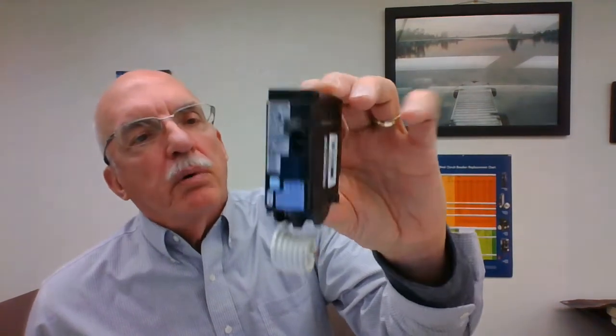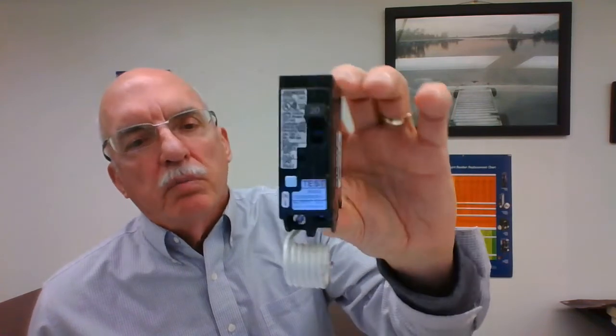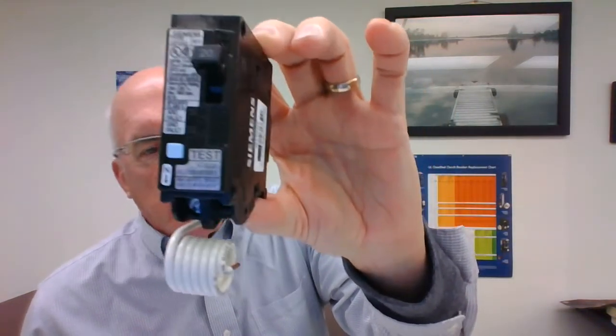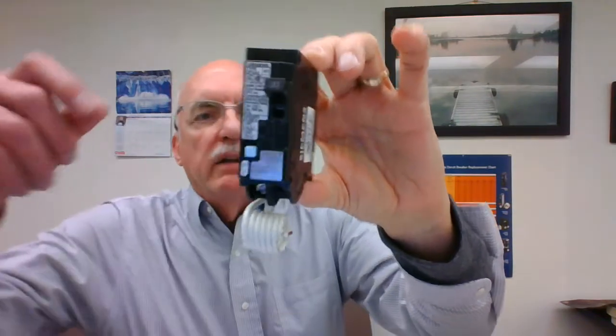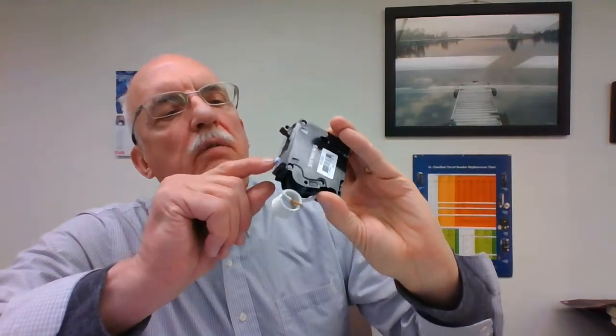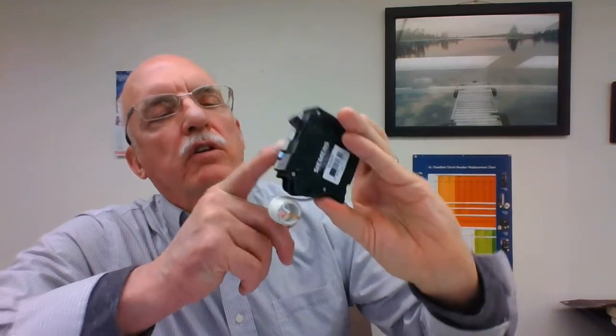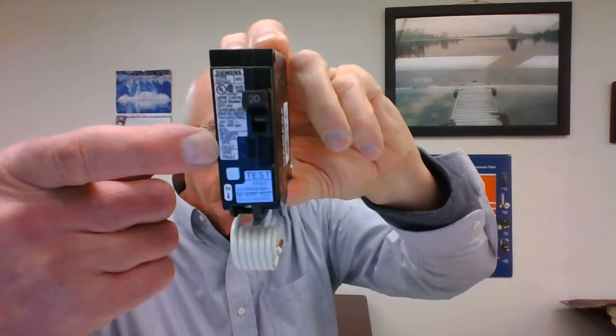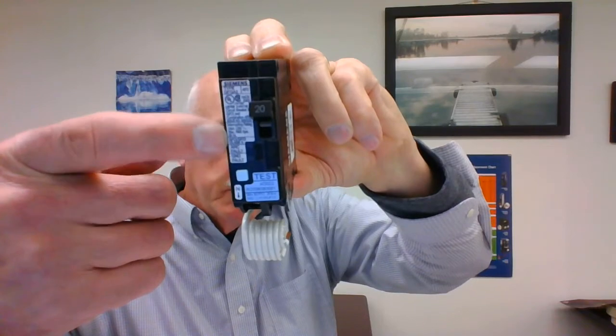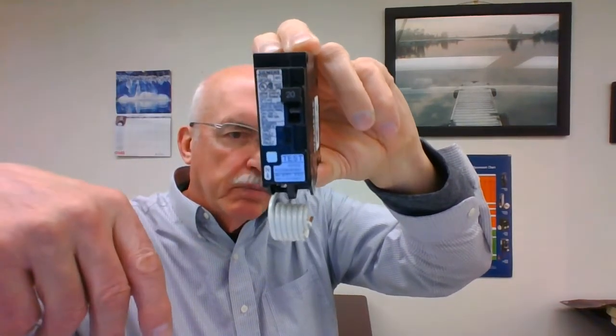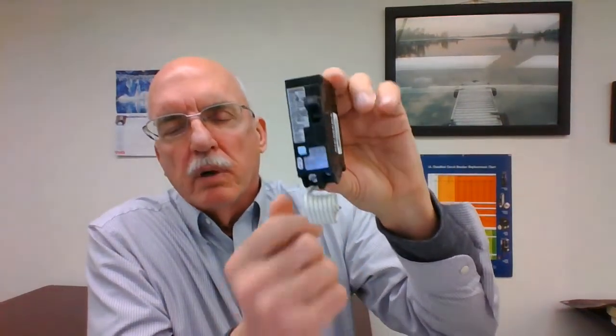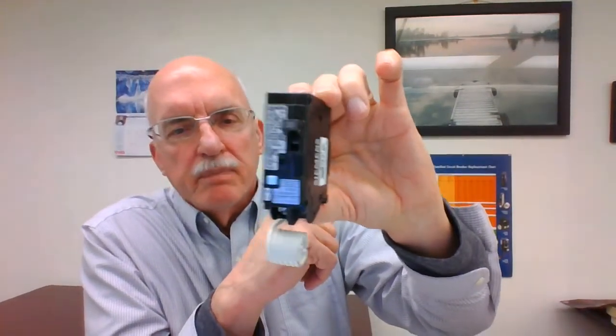So if you install this breaker, this is a Siemens breaker, you could see that it has 2 pilot lights on there, 2 indicator lights here, and one is for arc fault and one is for ground fault. So when this trips out, it will tell you what kind of protection it tripped out on. And then, of course, you have your test button here, which you are supposed to test these devices monthly.